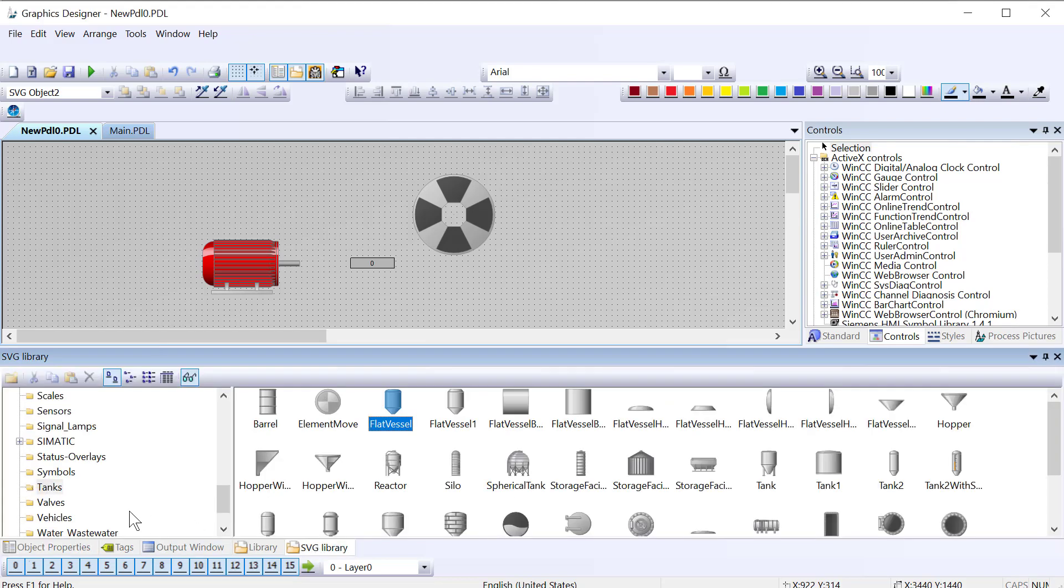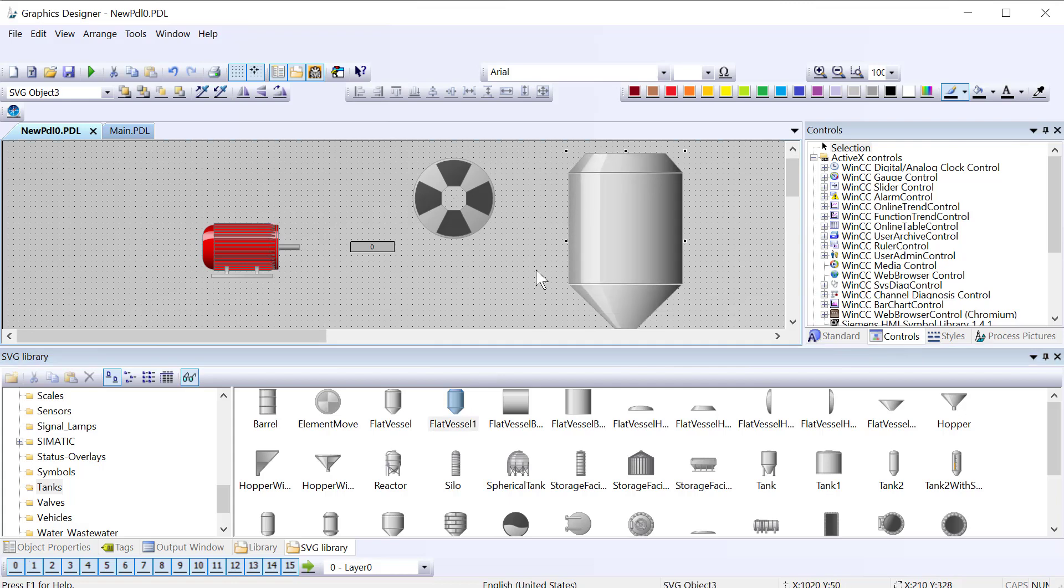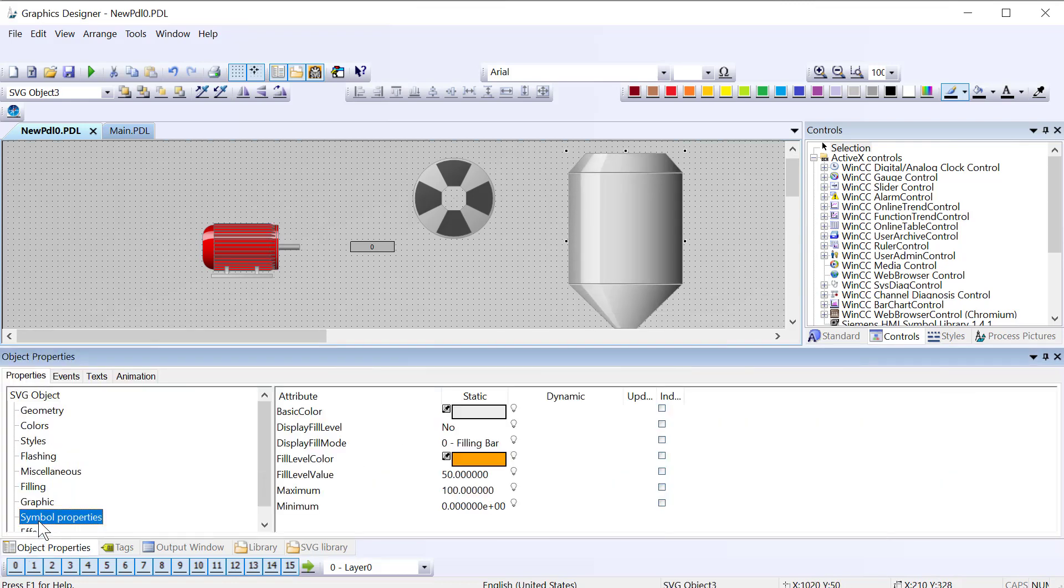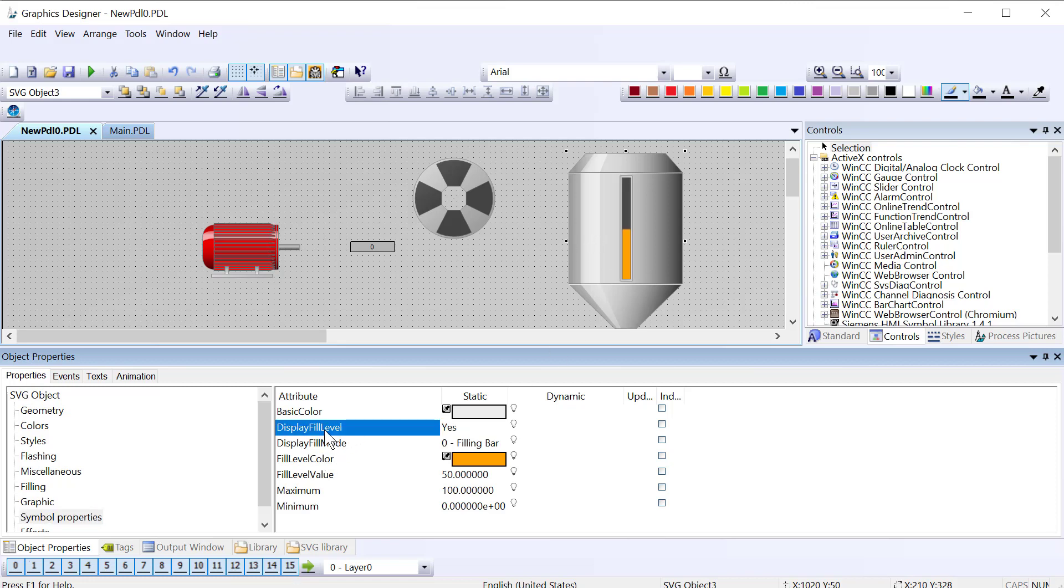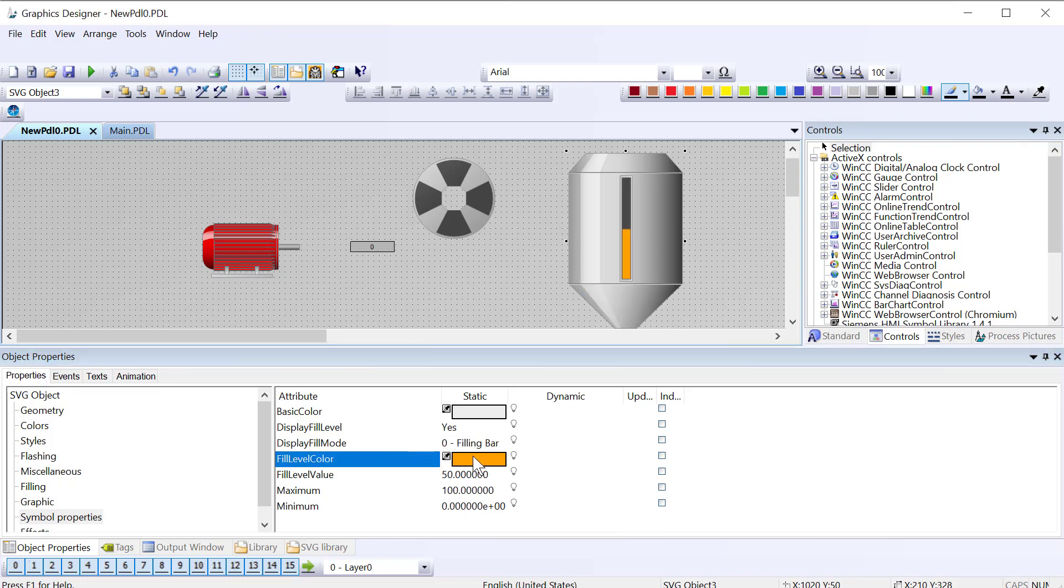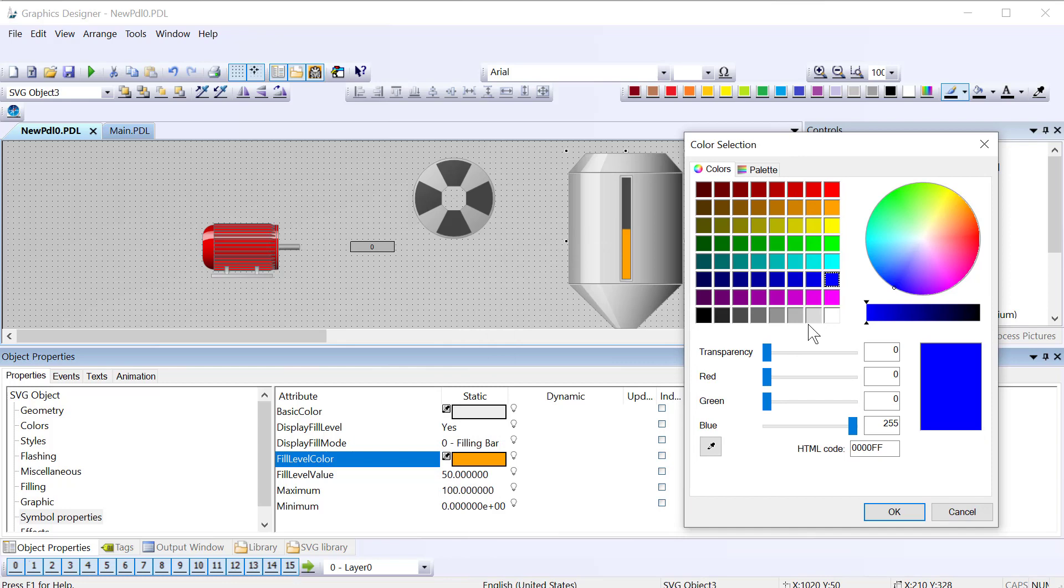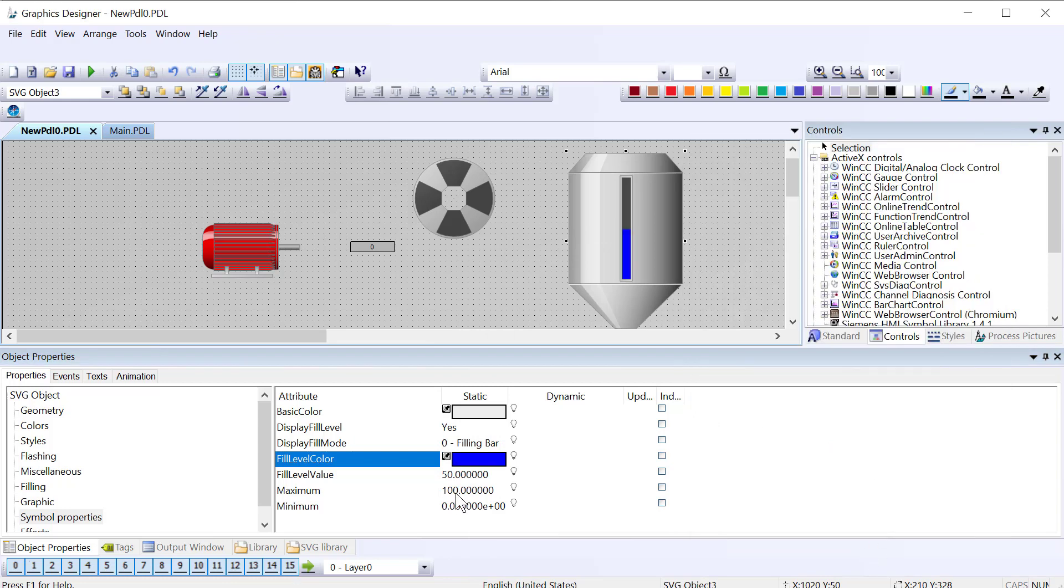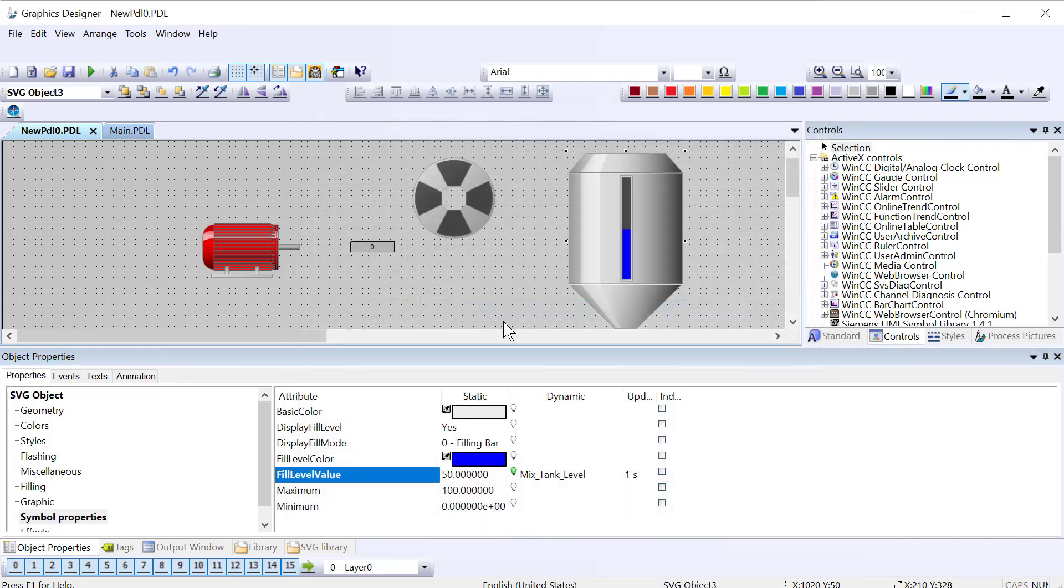We go back to the SVG library and look in tanks. I found this the other day when I was teaching a class. I'm just going to pull a tank out and some of these actually have some pretty nice properties. Here you can see that they have a fill window and you can do a reflective filling or you can do a filling bar and then you can animate the color as well. On my fill level I'm just going to attach my tank level tag and then I'm going to animate the color.